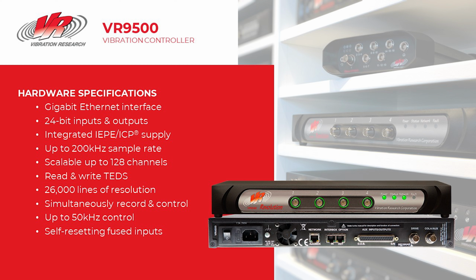With an integrated IEPE ICP supply, the 9500 can supply power, up to about a 4 milliamp signal, to any accelerometer or transducer that complies with those common standards for the front inputs of the VR9500.